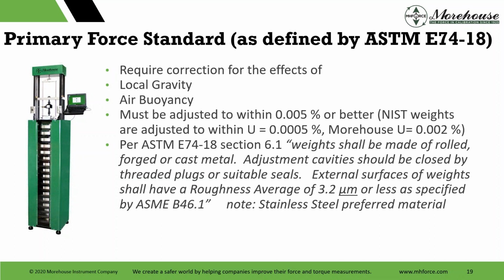And then per ASTM E74-18 section 6.1, they start talking about how the weight shall be made of rolled, forged, or cast metal. Adjustment cavity should be closed by threaded plugs or suitable seals. External surface of the weight shall have a roughness average of 3.2 micrometers or less, specified by ASME B46.1, which is interesting. And stainless steel is preferred. Why stainless steel? Because it's not magnetic. Any weight that can become magnetized can change.